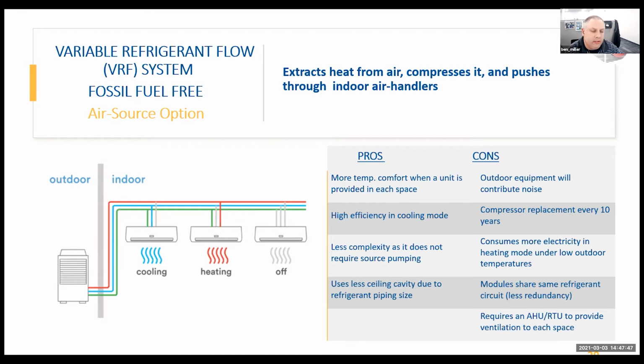And then the other option that we would propose for renovations that we use a lot is the variable refrigerant flow VRF systems, which are fossil fuel free. This extracts heat from air, compresses it, and pushes it through indoor air handling units. Pros for this system are more temp comfort when a unit is provided in each space, high efficiency in cooling mode, less complexity as it does not require source pumping, less ceiling cavity space due to refrigerant piping size. Some of the cons of this unit is equipment will contribute to noise, compressor replacement every 10 years, consumes more electricity in heating mode under lower temperatures. Modules share the same refrigerant circuit, requires an air handling unit or RTU to provide ventilation at each space.